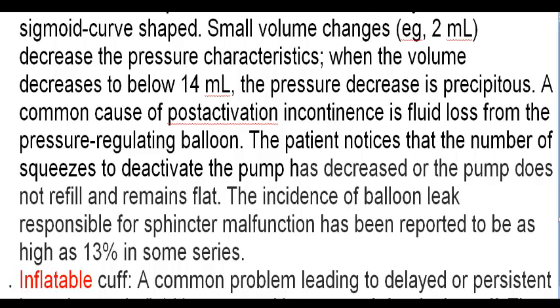A common cause of post-activation incontinence is fluid loss from the pressure-regulating balloon. The patient notices that the number of squeezes to deactivate the pump has decreased or the pump does not refill and remains flat. The incidence of balloon leak responsible for sphincter malfunction has been reported to be as high as 13% in some series. Inflatable cuff.